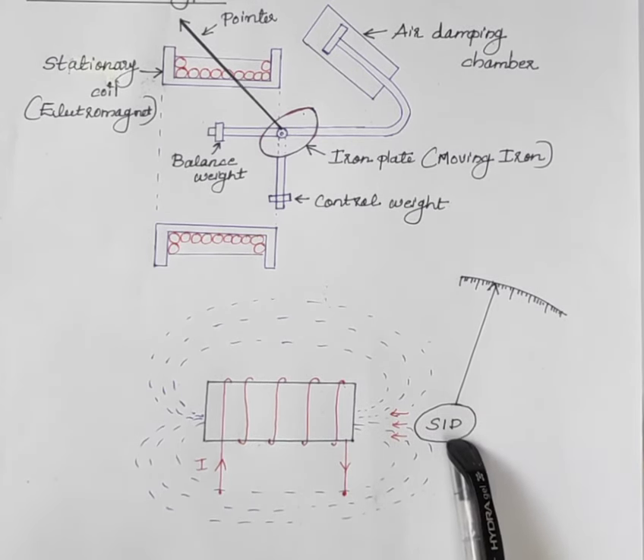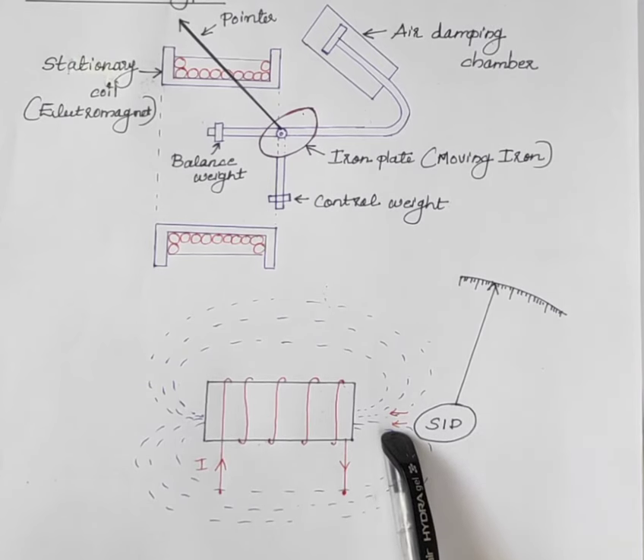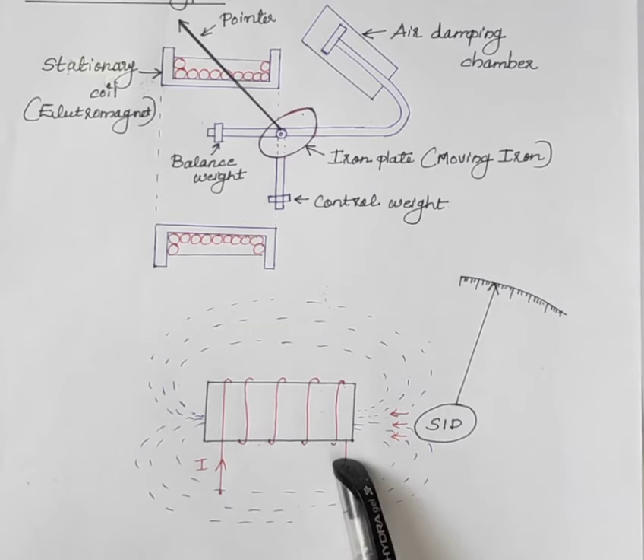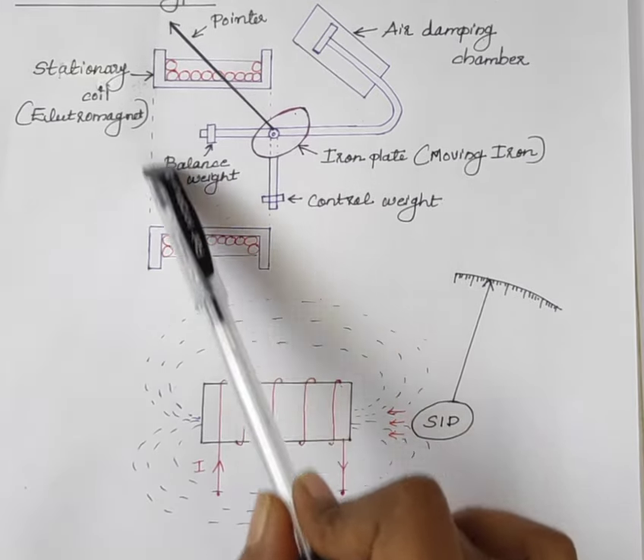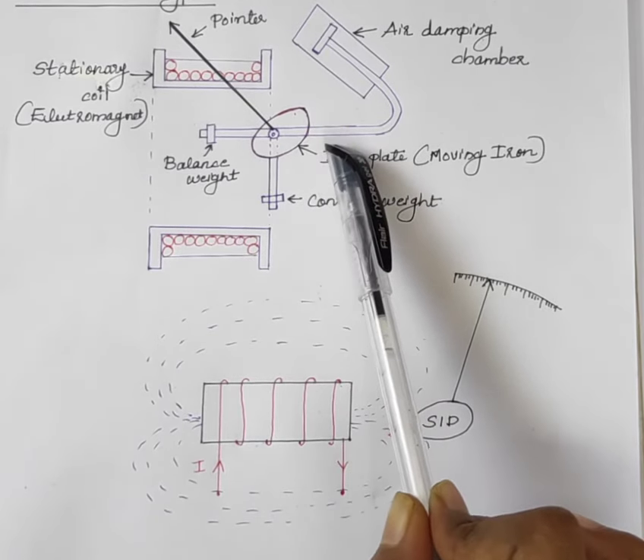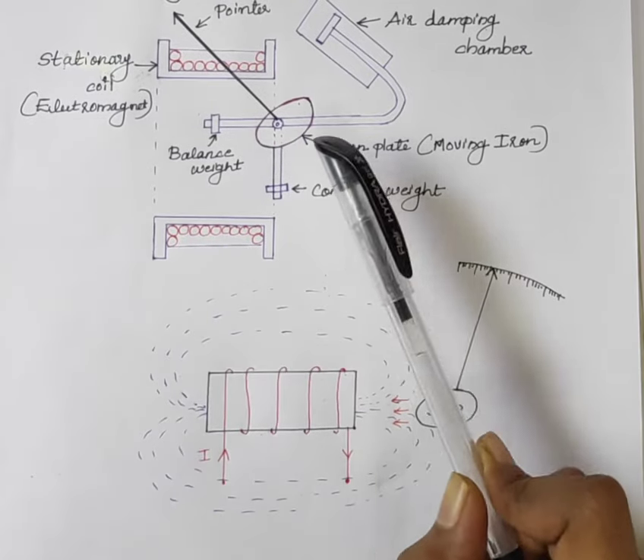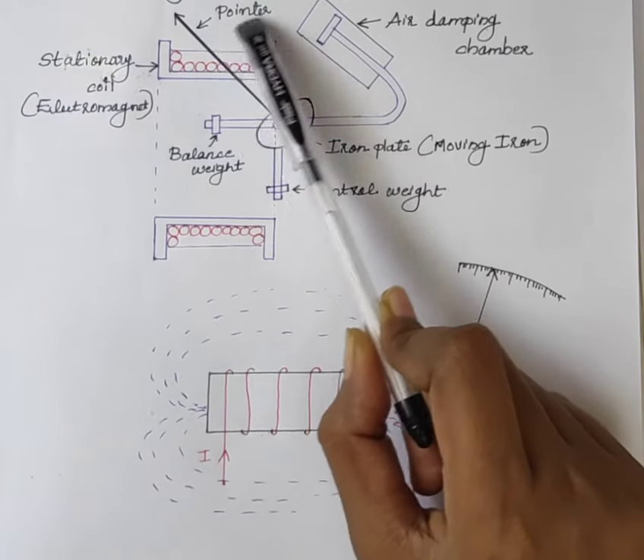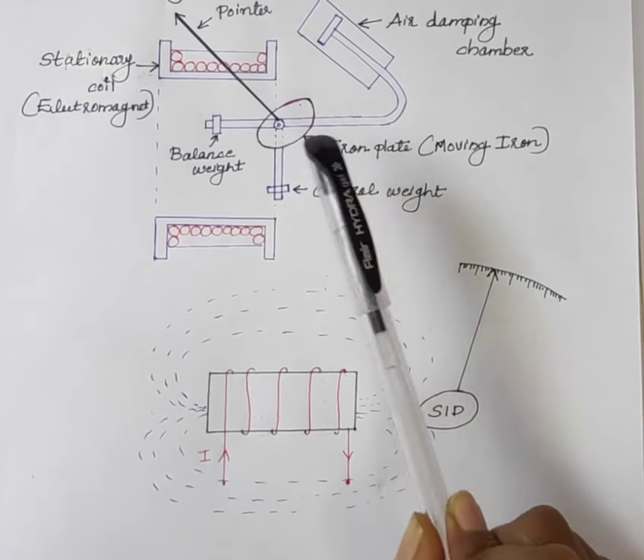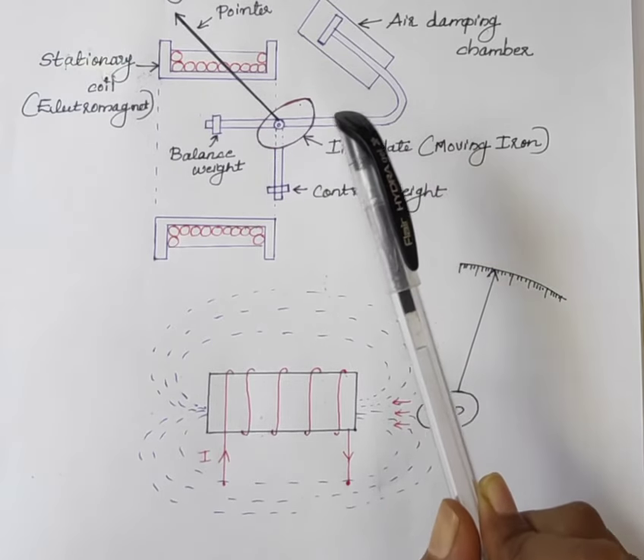This soft iron disc is attached to the moving system. So when the soft iron disc is attracted by the electromagnet, the pointer shows the reading which is proportional to the magnitude of current passing through the stationary coil. This one is the current carrying stationary coil — it acts as an electromagnet and a soft iron disc is placed near to it. When current passes through the coil, it becomes an electromagnet and the iron plate is attracted, and the pointer shows the corresponding reading. The instrument in which the iron plate is attracted from the weaker field towards the stronger field is known as attraction type instrument.